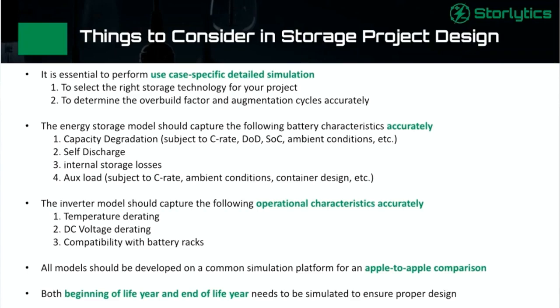And that varies over time, varies over your SOC range. You need to be able to capture that. Your auxiliary load assumptions—you have your C, it varies with your C rates, your temperature, your container design, liquid cooling versus air cooling. So all these factors play into your auxiliary load assumptions as well. You need to have accurate, validated models for this to come up with good design assumptions.